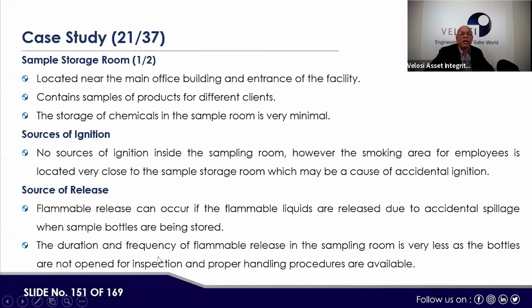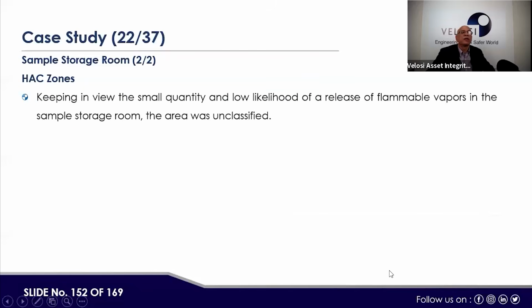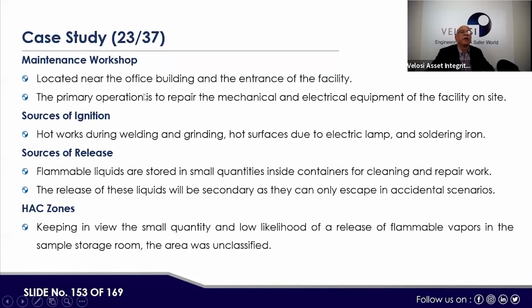The duration and frequency of flammable release in the sampling room is very low, as the bottles are not opened for inspection and proper handling procedures are available. Keeping in view the small quantity and low likelihood of released flammable vapor in the sample storage room, the area was unclassified. Next, the maintenance workshop, located near the office building and entrance of the facility.